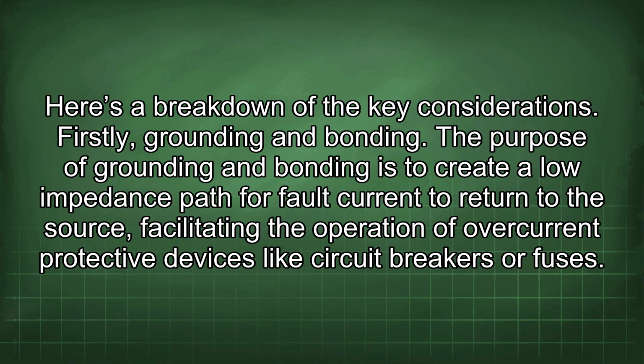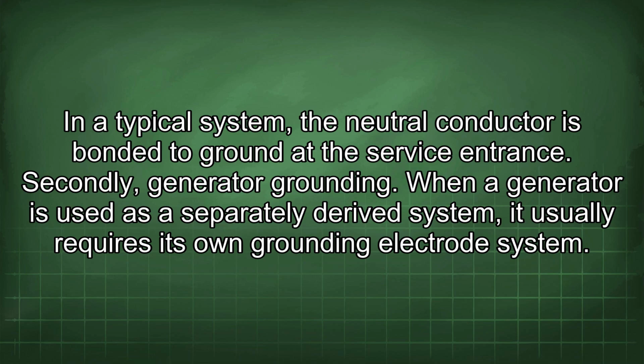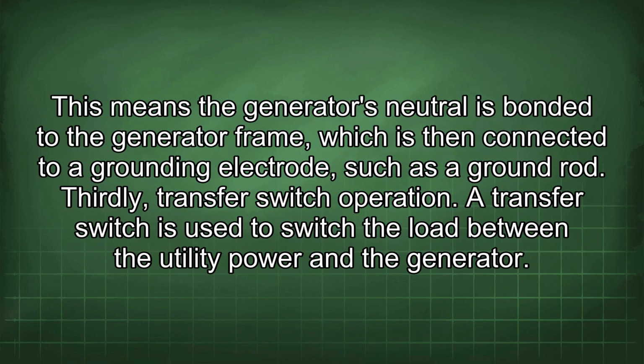Firstly, grounding and bonding. The purpose of grounding and bonding is to create a low impedance path for fault current to return to the source, facilitating the operation of overcurrent protective devices like circuit breakers or fuses. In a typical system, the neutral conductor is bonded to ground at the service entrance. Secondly, generator grounding. When a generator is used as a separately derived system, it usually requires its own grounding electrode system. This means the generator's neutral is bonded to the generator frame, which is then connected to a grounding electrode, such as a ground rod.